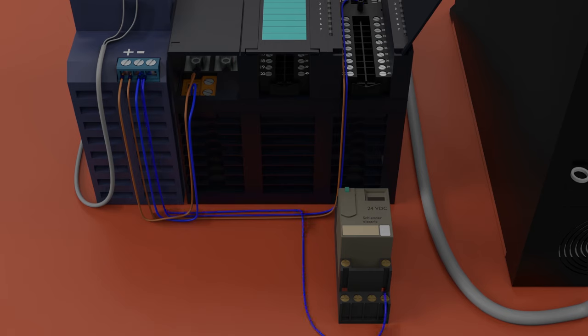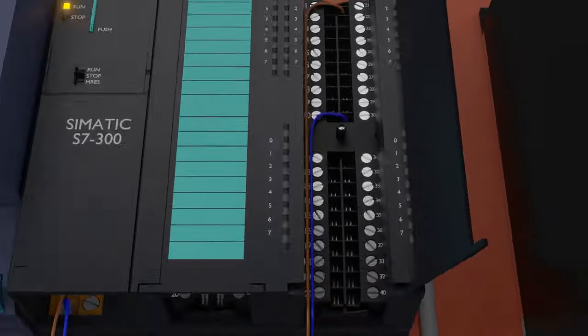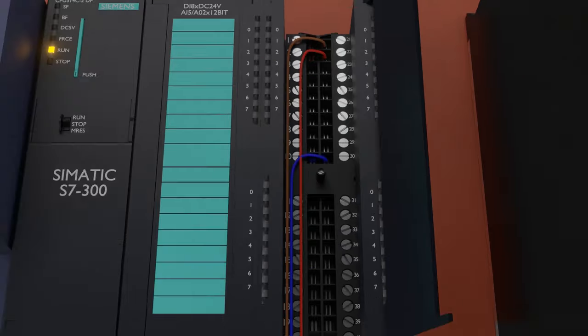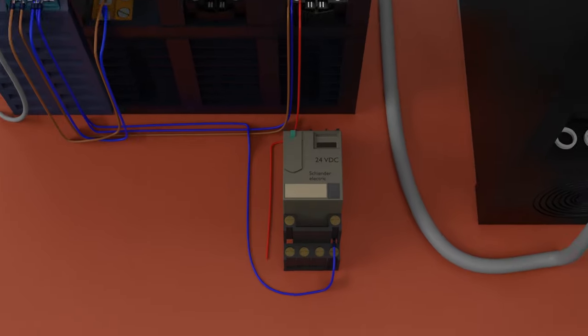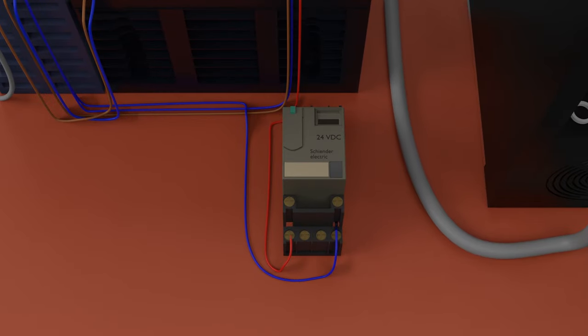Now we have to connect a digital output signal from the PLC to be able to turn on this relay. So we will connect a wire from digital output terminal 22 of the PLC to the relay A1 terminal. Now when output Q124.0 goes high, this relay will turn on.